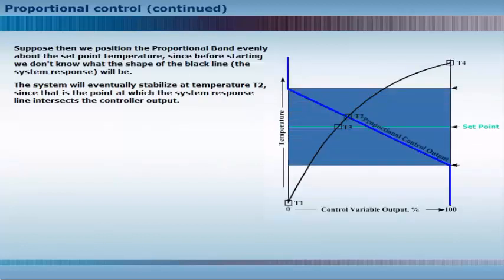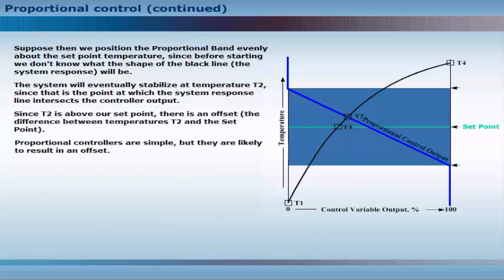Suppose then we position the proportional band evenly about the set point temperature, since before starting we don't know what the shape of the black line will be. The system will eventually stabilize at temperature T2, since that is the point at which the system response line intersects the controller output. Since T2 is above our set point, there is an offset, the difference between temperatures T2 and the set point.